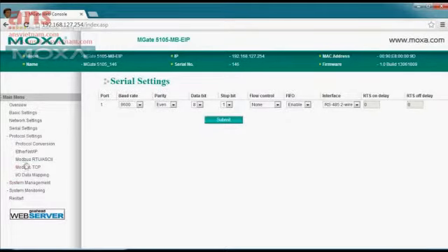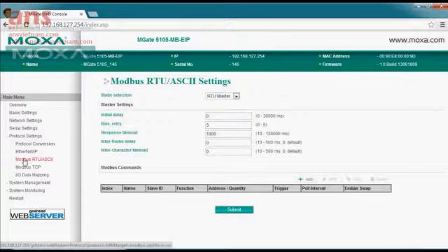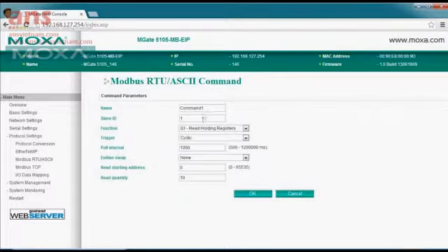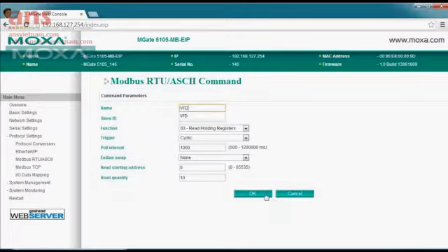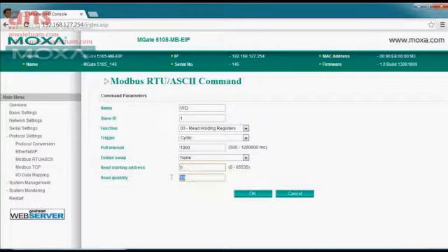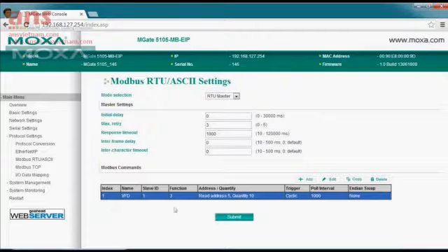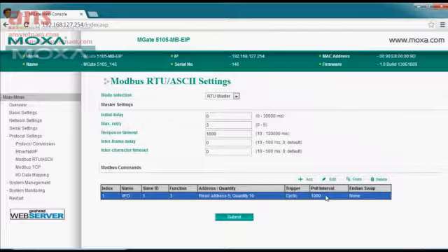Once we've done that, we'll define the values we want to look at from the PLC. We'll click on Modbus RTU. Here, the MGate is going to be the master, and we'll add some registers to pull. We'll call this the VFD, and we're going to read data starting from register 5 — let's read 10 registers — and submit these for a polling cycle. At the bottom of the screen you can see this data will be pulled periodically every 1,000 milliseconds, or one second. You can change that if you prefer. Let's make these changes.